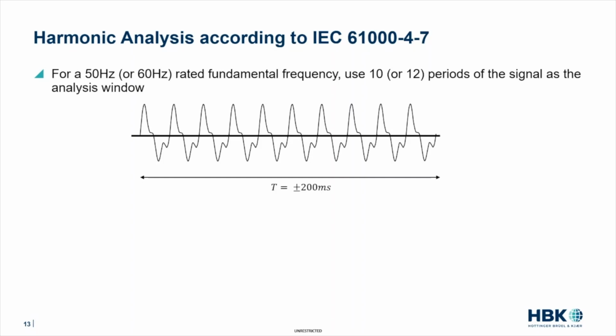So for example, if you have a 50 Hertz system or a power system with a nominal frequency of 50 Hertz, the standard says that you should take a time signal of 10 periods, which is then approximately 200 milliseconds. And this time signal you should use to determine your harmonics. So it's not allowed to determine the harmonics, for example, using a single period or 2 periods. You should always use 10 periods in case of a nominal frequency of 50 Hertz and 12 periods in case of a nominal frequency of 60 Hertz, so that in any case you always end up with a time signal of approximately 200 milliseconds. So that is one of the things that the standard prescribes.